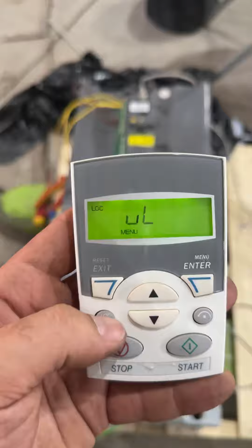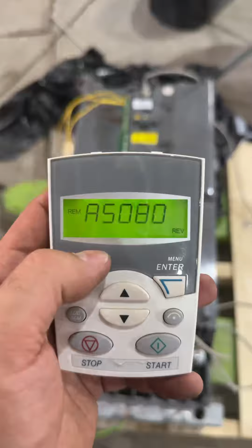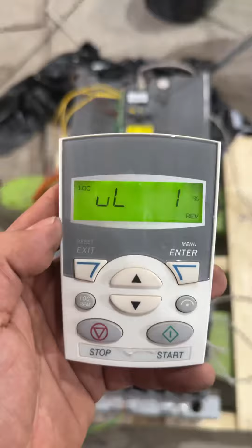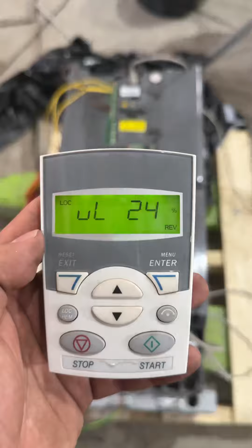Now if I press enter, it works, but if it's on remote mode, you are facing this code, so it needs to be changed to local. Now I change to local, press enter. Now the old data is copying from the VFD to the control panel.